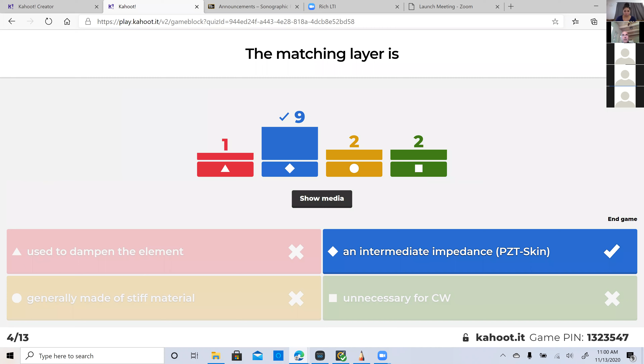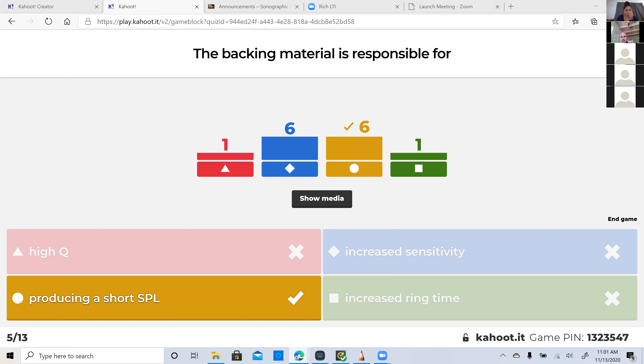The backing material is responsible for... okay. Yes, I'm sorry, I got a little distracted there. Backing material is responsible for a short spatial pulse length. That's why we do that. Increased sensitivity? No, it decreases our sensitivity. So the backing material has a lot of bad features, but that one feature of a short SPL is so important that they do it anyways.